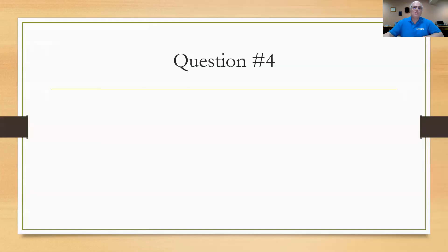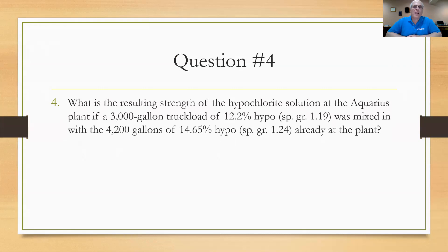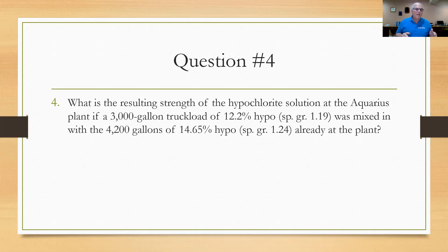Question number four: What is the resulting strength of the hypochlorite solution at the Aquarius plant if a 3,000-gallon truckload of 12.2% hypo with specific gravity 1.19 was mixed into 4,200 gallons of 14.65% hypo with specific gravity 1.24 already at the plant? This is a real-world situation — a truck arrives when residual solution is still in the tank, and you need to know the combined strength to continue disinfecting properly. The formula for mixing two solutions is: percent strength of mix equals pounds of chemical from solution one plus solution two, divided by total pounds of solution, times 100.